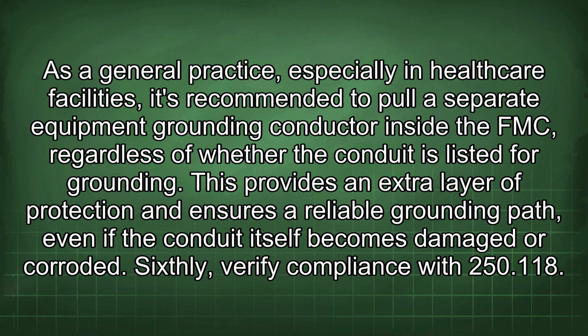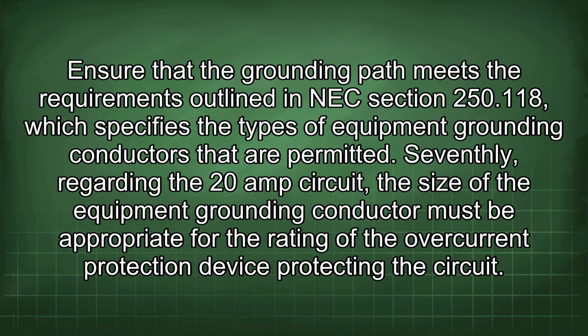This provides an extra layer of protection and ensures a reliable grounding path, even if the conduit itself becomes damaged or corroded. Sixthly, verify compliance with 250.118. Ensure that the grounding path meets the requirements outlined in NEC section 250.118, which specifies the types of equipment grounding conductors that are permitted. Seventhly, regarding the 20 amp circuit, the size of the equipment grounding conductor must be appropriate for the rating of the overcurrent protection device protecting the circuit.